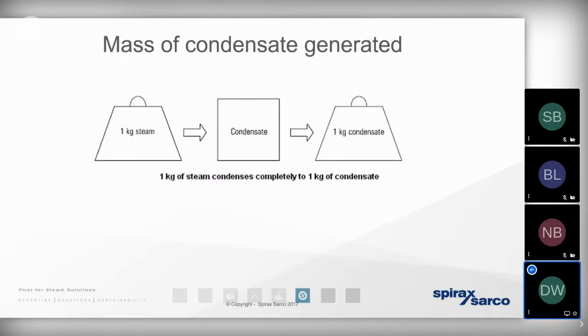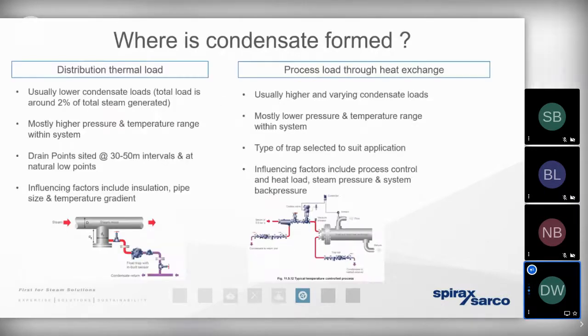And remember, with it being a compressible gas, a higher pressure steam distribution network will result in steam existing at a lower volume. We've mentioned that condensate exists wherever we've got a heat loss, wherever the steam gives up its heat energy. And the steam's going to give up its heat energy in two different places. First, the heat losses in the distribution network, which we don't want. And second, the heat losses that result in the steam giving up its heat energy at the process, which, of course, we do want. If we look at the heat losses in the distribution pipework first, we typically work on a rule of thumb that approximately 2% of all of the steam being generated is going to result in condensate existing in the distribution pipework. So, for example, if we're generating 10,000 kilograms per hour of steam, we expect that approximately 200 kilograms per hour will change state and produce condensate in the distribution pipework.